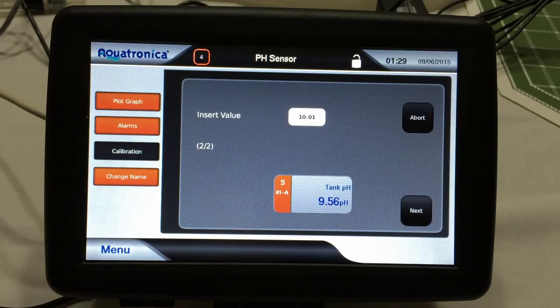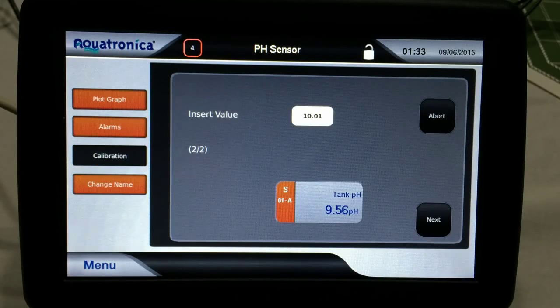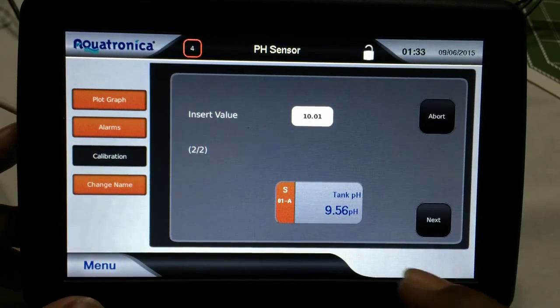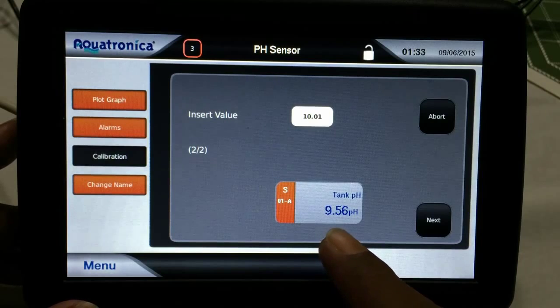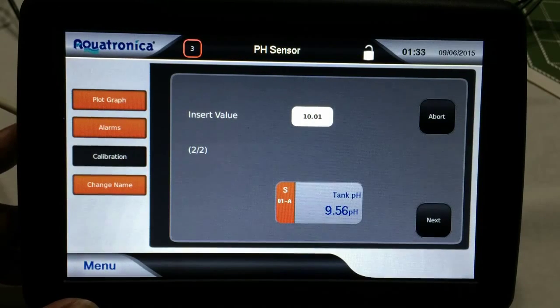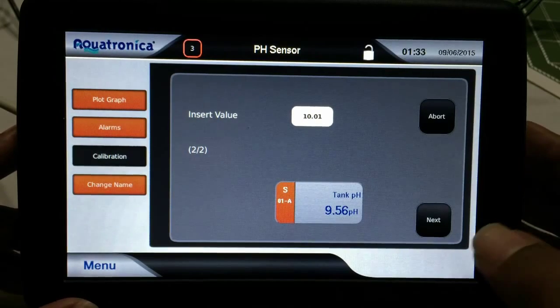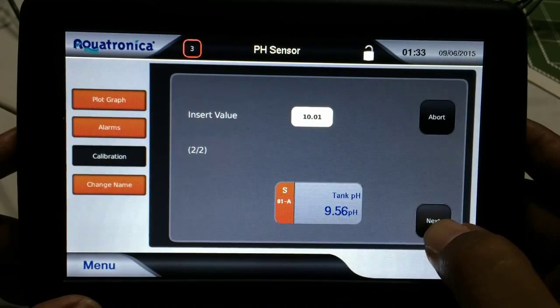Some people do it for shorter periods of time. You can look on Aquatronica's website. They'll give a recommended time for their probes. So I'm going to let this stabilize for a little bit, and then when it does, I'll hit next, and that'll be it. Okay, it's been sitting for about 4 or 5 minutes, and basically what you're looking for is this number to stabilize, and it's pretty much stabilized at 9.56. So I know it's not going to be changing. So once I hit next, that will become the reference value for that point.